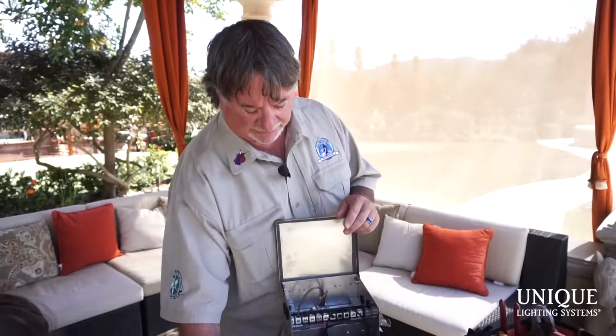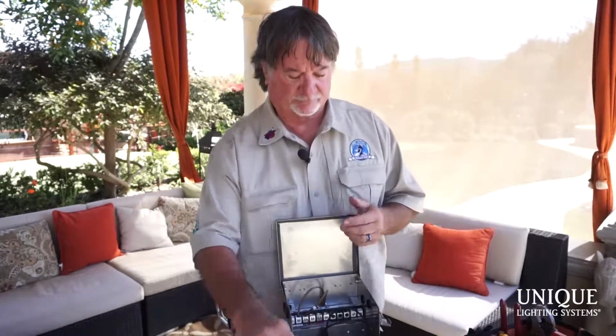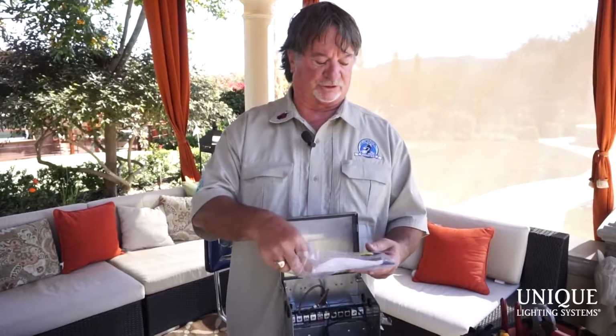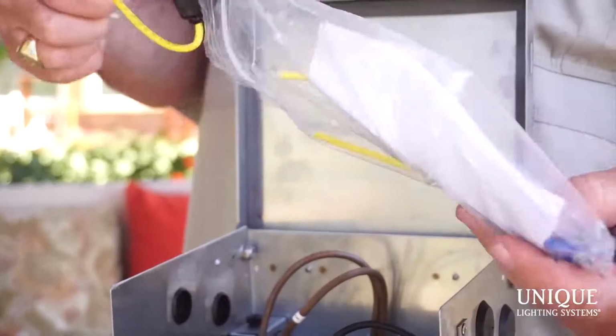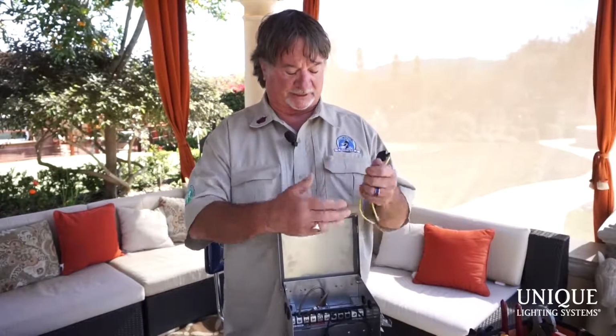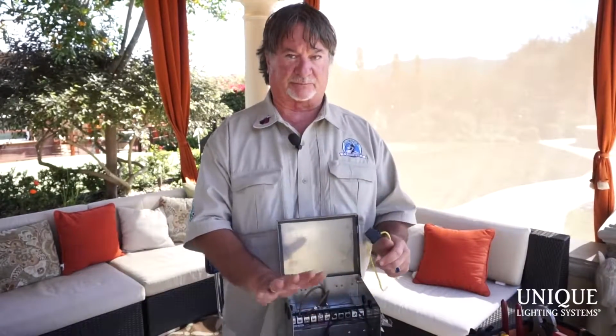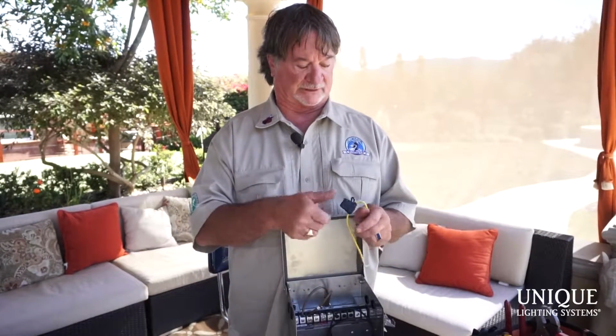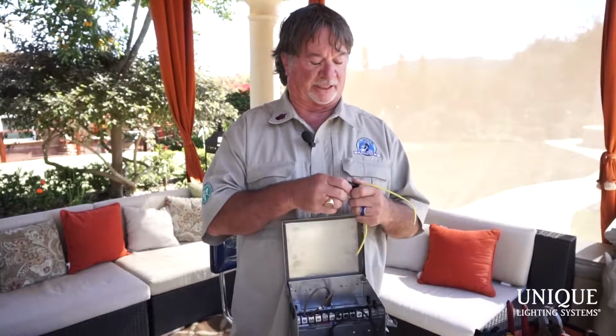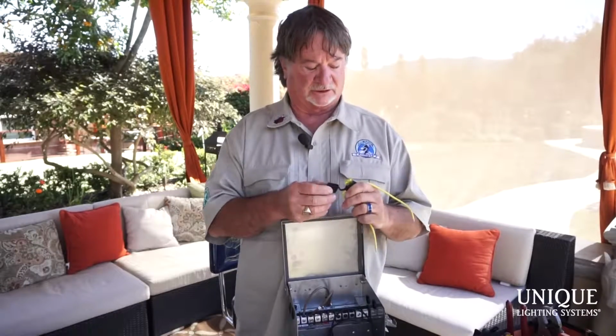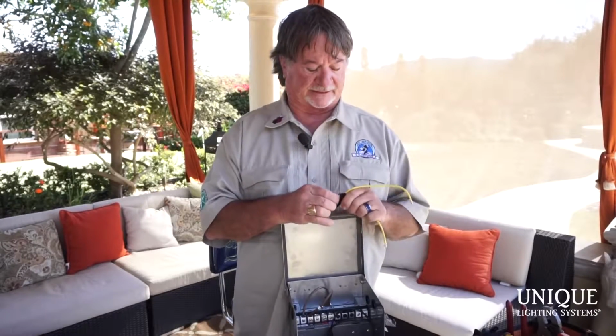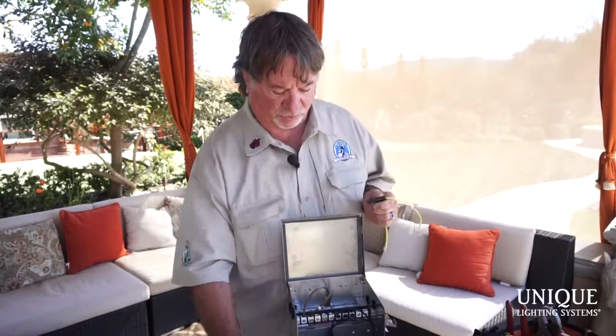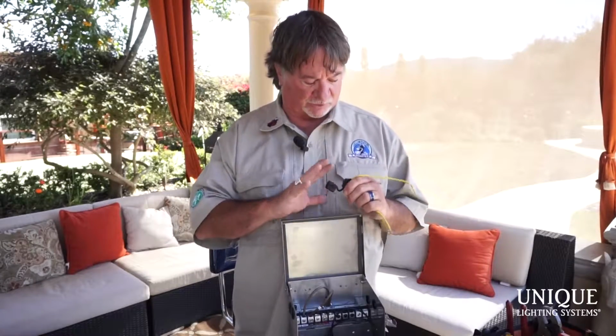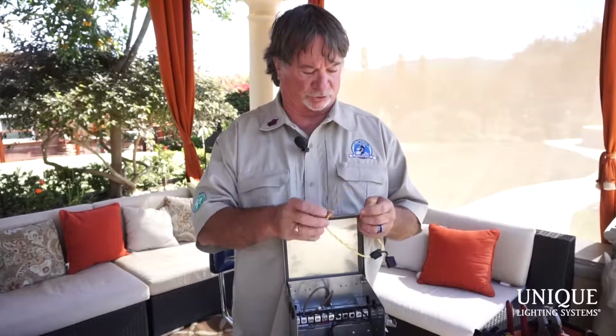Now the next thing I want to show you: we give you several fuses here in a little fuse bag. This is added protection. I've already protected myself with the primary fuse that'll protect me from downstream and the 110 side. It comes with a 20 amp fuse pre-installed. I'm going to set that aside for a minute, keeping this open, because I want to make sure I fuse per load too.